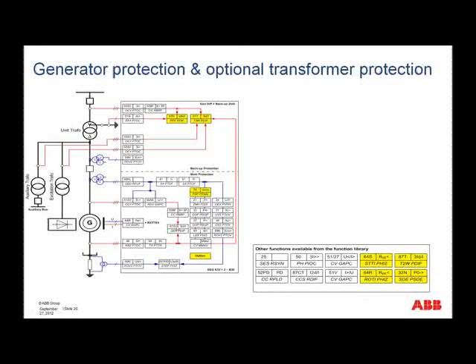It has the 87G. But now we can include protection for the step-up transformer, and here we would be looking at functions like the 87N, or restricted earth fault, 87T, which is then the differential protection for the transformer, and it would have as its boundary this CT here, these two CTs here, and in this case, although it's an 87T function, it's actually got the functionality of 87O in that it is including both the step-up transformer as well as the generator.